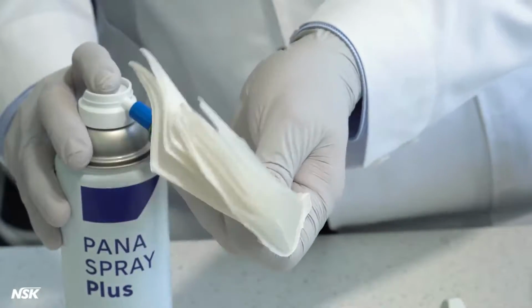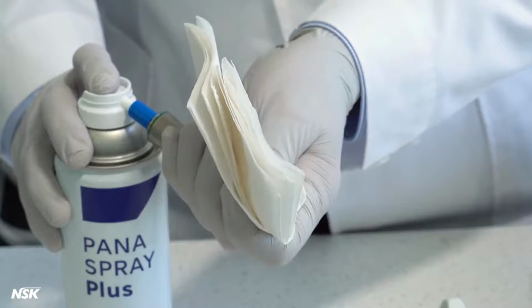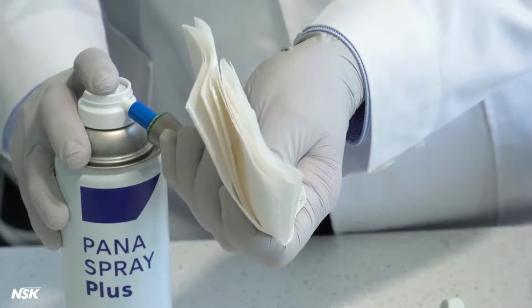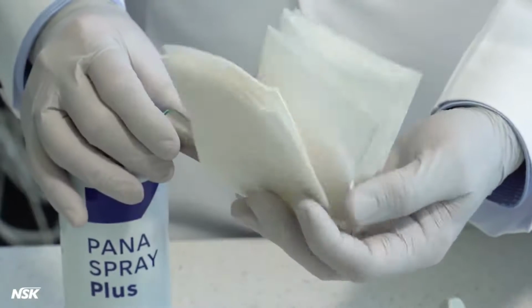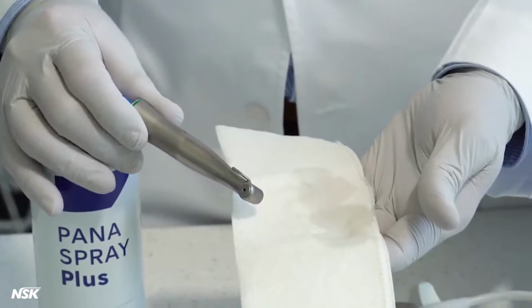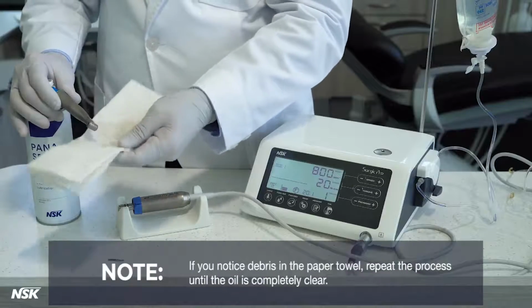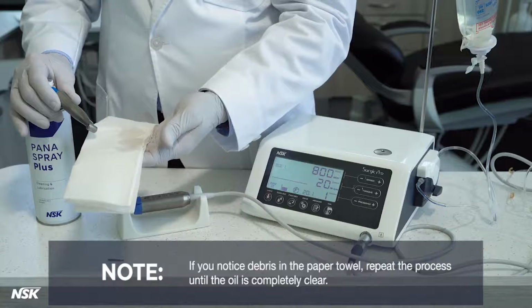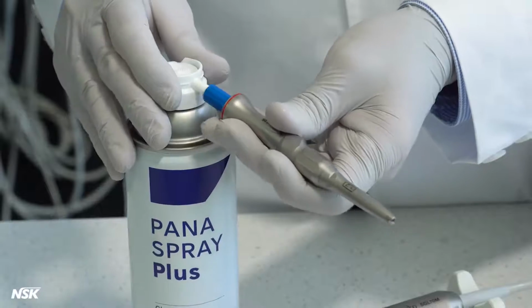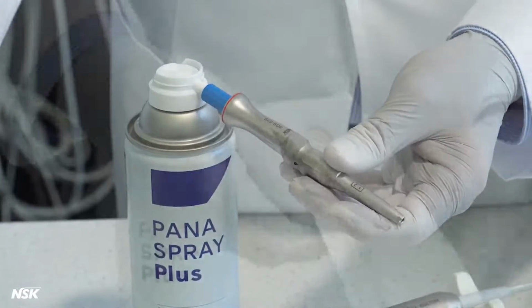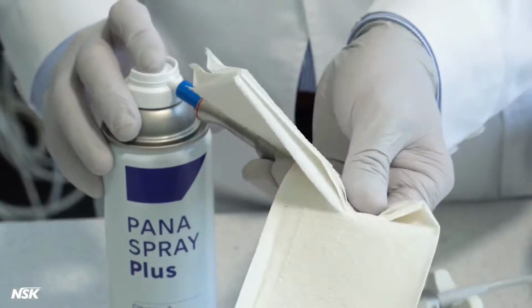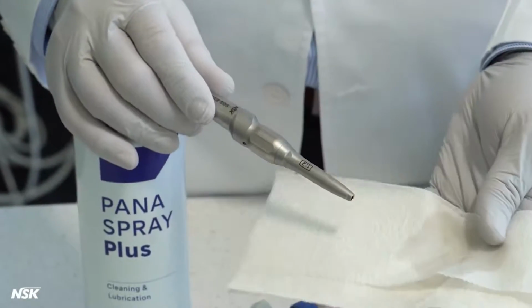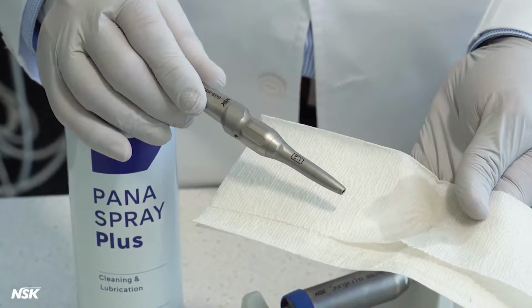in upright position. Make sure the oil flushes the debris out of the attachment and clear oil comes out of the head. This should take 4 to 5 seconds. If you notice debris on the paper towel, repeat the process until the oil is completely clear. Due to the design of straight surgical attachments, extra attention to maintenance is required. The attachment is ready now to be autoclaved using the FDA-approved pouch.